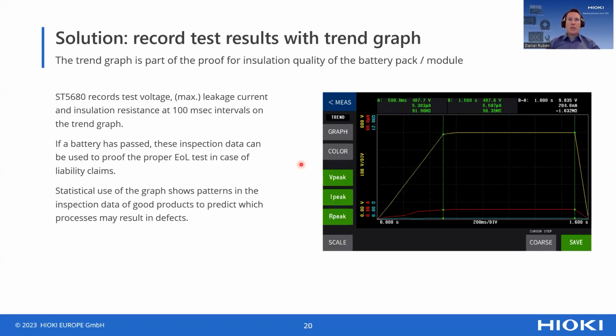Our solution is to have the data of the test being recorded, even in the form of a trend graph. So this makes it again possible for the customer to have a very good level of interpretation. As you can see, we are able to measure leakage current and insulation resistance at a 100 millisecond interval. Having that kind of waveform makes it much better to determine whether anything has happened during the testing process. And if everything has happened in a good way, you have a pass and you have a level of current leakage which is completely satisfying.